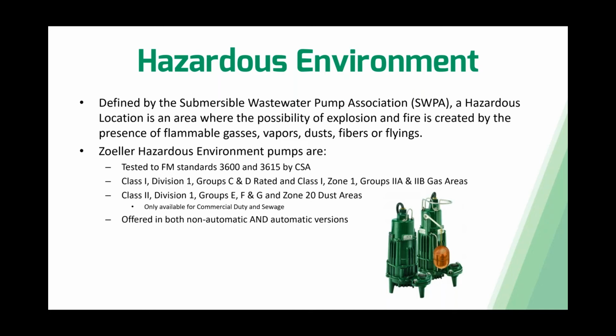Whereas in a non-automatic pump or system, you would need a control panel with intrinsically safe relays and low current float switches. So you're adding cost by going the non-automatic way and adding a control panel and adding float switches. Whereas with the automatic version, the only thing you really need to do is we offer a seal fail panel, because these pumps come with seal fail indicators to let you know if something has happened, the seal's failed, water's getting in the pump some sort of way. To give you an idea on cost savings, just by going the automatic version versus a non-automatic with a control panel and float switches, you're saving about 26%. So that's a huge amount.